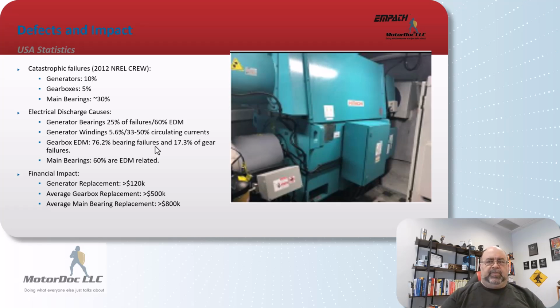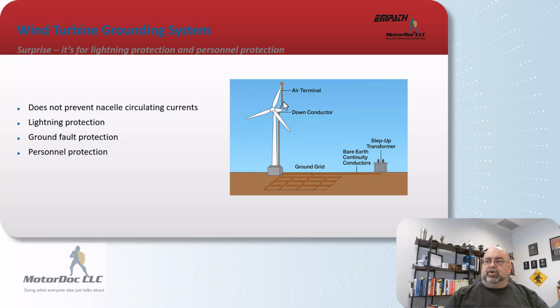So we've had data from multiple organizations, all started with the original wind company that suggested this. So we didn't discover anything. We discovered what the root cause was, and that is actually that the grounding protection when we're in the nacelle has literally nothing to do with grounding the nacelle. It has everything to do with lightning protection only. And when you consider the amount of current up there, now all of a sudden the small size of the ground leads makes more sense. So they do have personnel protection all the way up. That's a required standard as well. There's no standard calling for the nacelle to be grounded to earth.